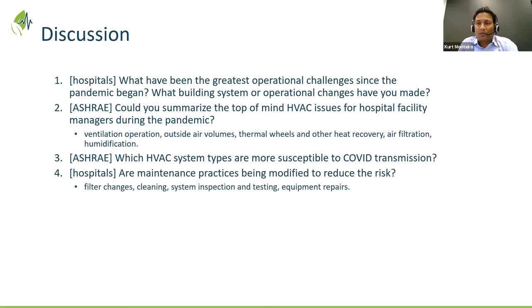Yeah, I think there's a significant risk if you try to run in and make changes without understanding your current HVAC system—there could be significant impact. One thing that's happened over the years with CSA Z317.2 is that the sterile core originally used to be negative to the OR, so the OR was positive to all adjacent spaces. The recent changes in the standard over the last decade switched it so the sterile core is positive to the OR, and the OR is positive to the clean corridor. So you have this cascade effect outward.